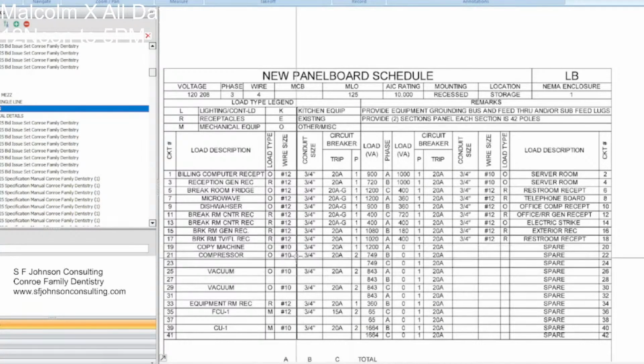And look on every panel, copy machine, compressor, vacuum, condensing unit, server room. You got to go to the power plan, find where those are, and do the physical measurement from that home run to panel LB or wherever it's going.